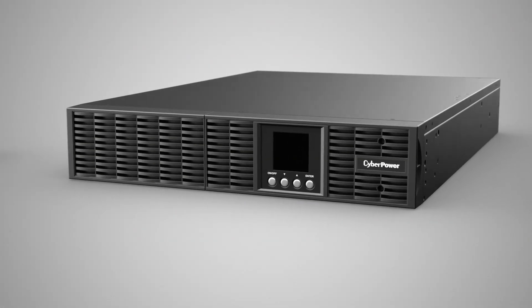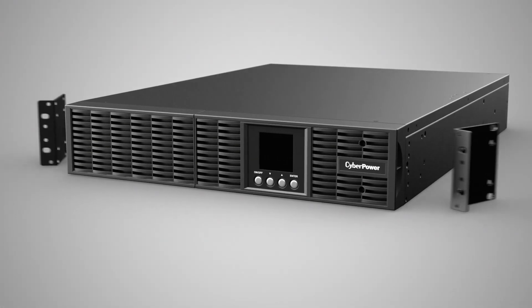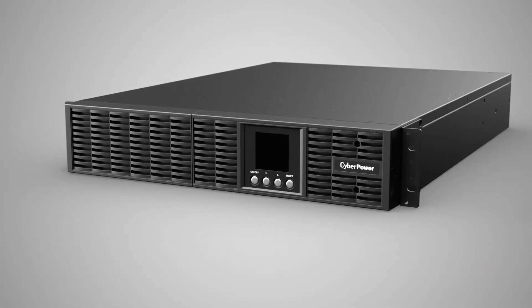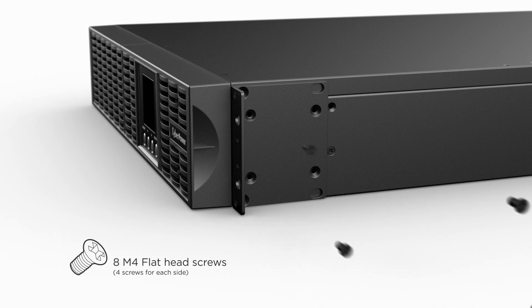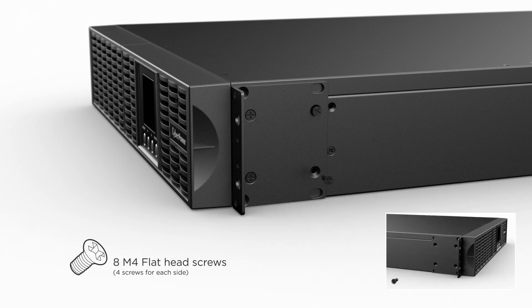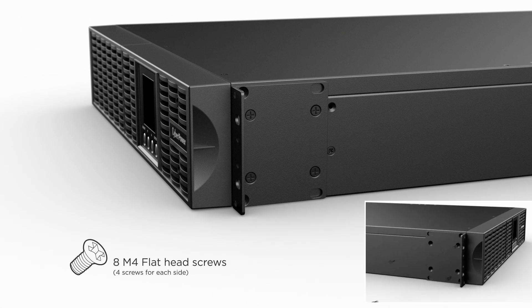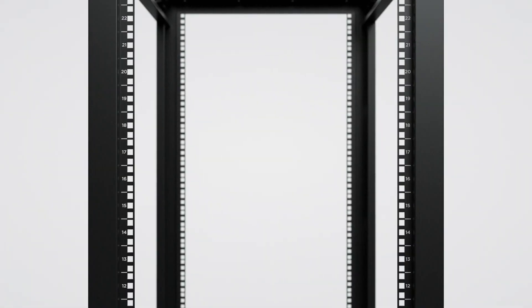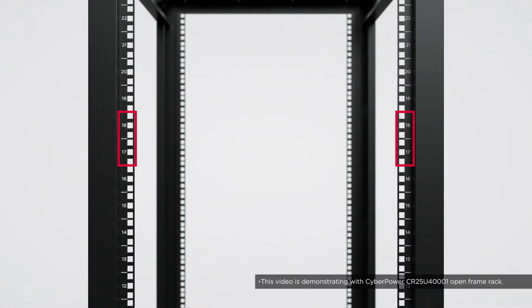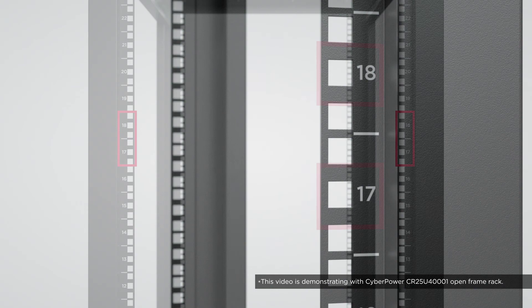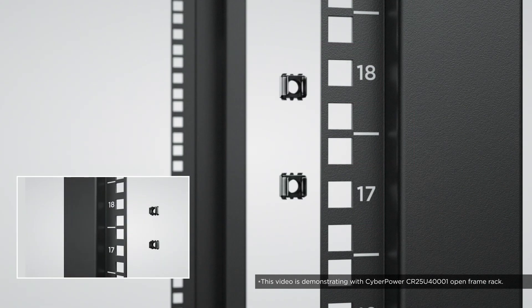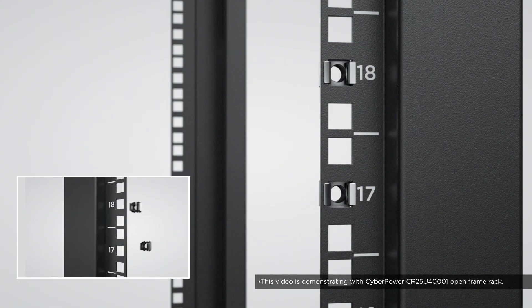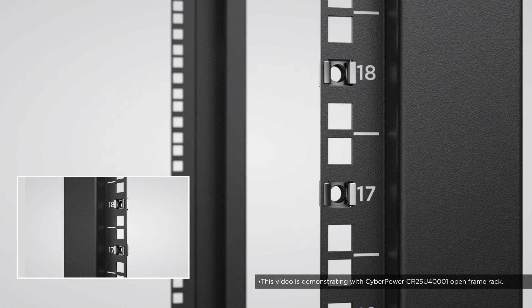Install the 2 Rack Mount Ears onto both sides of the UPS using 4 Flat Head Screws on each side. Then, choose two rack units for the UPS rack mount installation, and insert two cage nuts provided by the Server Rack into the middle holes of the two rack units on each side.